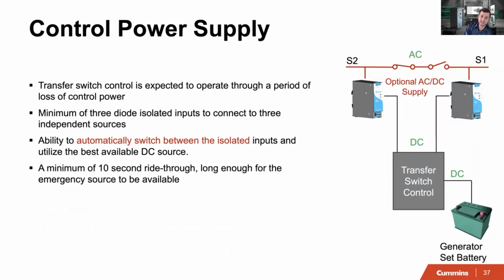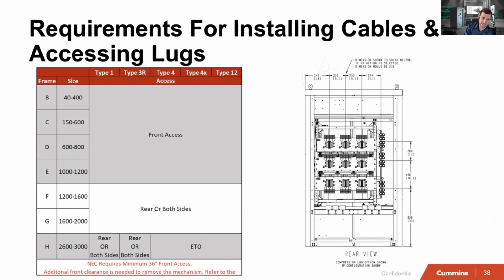The power supply is needed because we have a lot of critical information we're pulling from the transfer switch. The inputs on the controller are diode isolated. It has 3 different diode isolated inputs for higher reliability. And then the requirements for installing cables and accessing the lugs. You get front access for up to 1200 amps, and then you either have rear only or both sides. So when we designed this, again, we looked at a lot of installations in the field, and we wanted to make sure that it is easy to access the lugs or the cables, and if there's any service that is needed, we have that in mind.